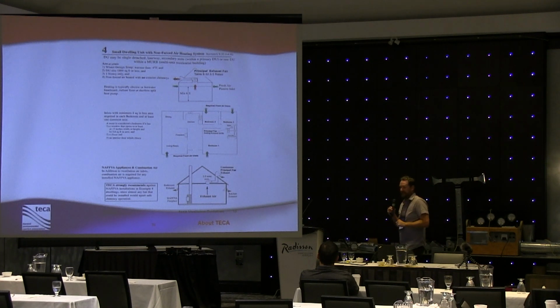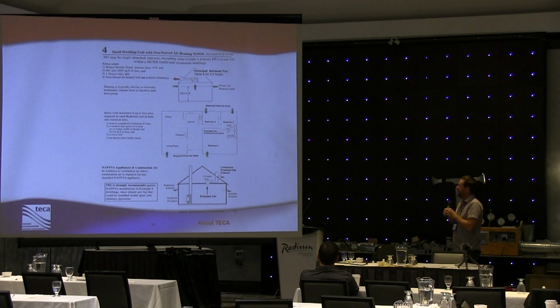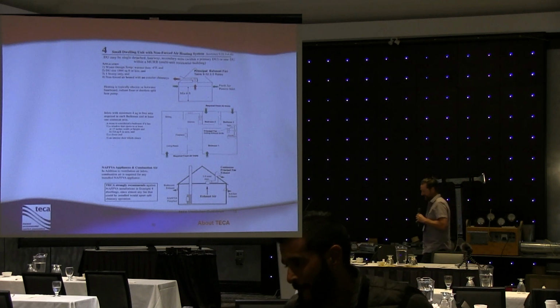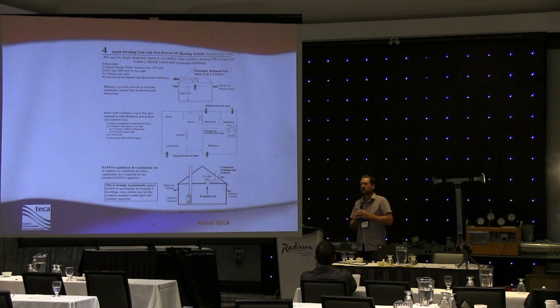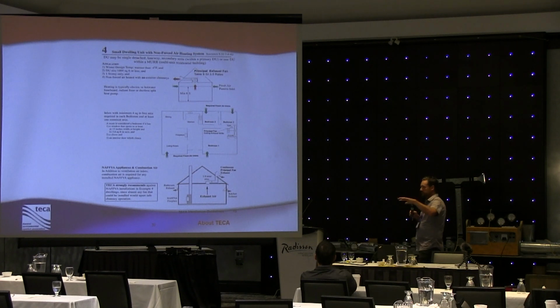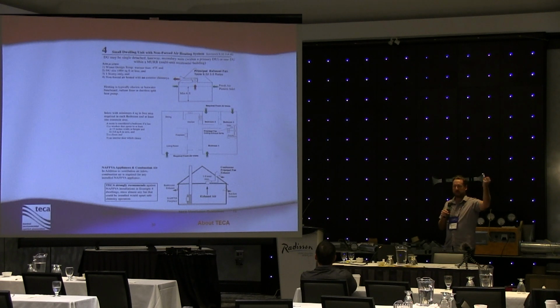So 1 story only. But I have seen this system installed in locations where there is 1.5 story, or basically not a split level so much, but perhaps there's a small living level, and then the upstairs they have had passive vents on. I've seen it installed like that, and that's exactly what happens. It's those lower level fresh air inlets. They allow fresh air to rush into the building, and the inlets in the upstairs bedrooms turn into exhaust grills. They don't actually allow the fresh air to migrate correctly. So you have to be very, very cautious of that.